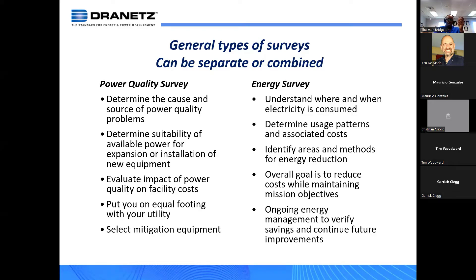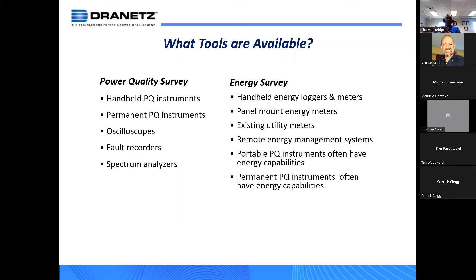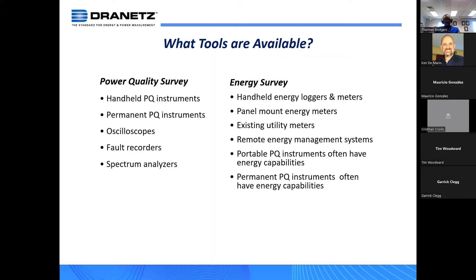The key is which tools are available for a given task. For power quality, handheld PQ instruments are probably the most common. A survey is usually short-lived — not permanently installed. If a client is currently having PQ problems, the natural reaction is to go out with a portable, monitor the point of common coupling or where the source of the PQ problem might be. The instrument stays there until you record the data, then analyzing the data and making the determinations leads to selecting the correct mitigation.